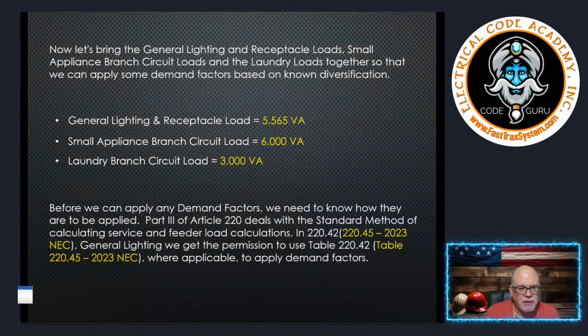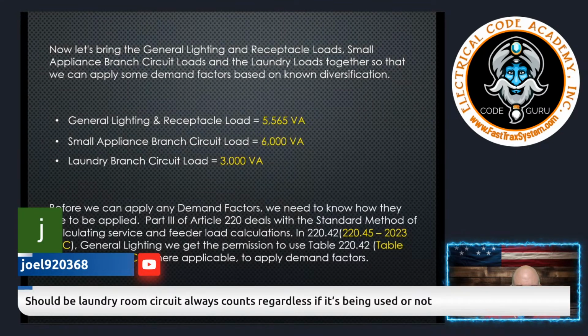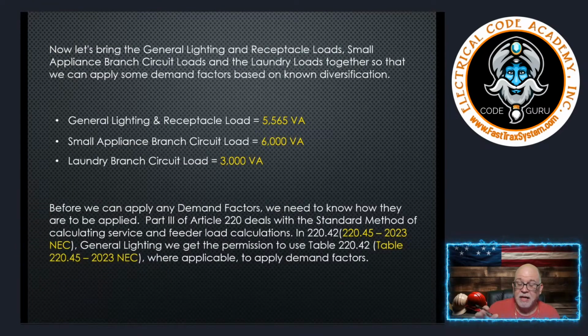Let's see here. Question we had: should the laundry room circuit always be counted regardless if it's being used or not? You have to have a laundry circuit, period. Unless you're dealing with a multifamily dwelling that has a laundry facility on site that is available to all of the tenants or all of the renters, then it doesn't matter whether you use that laundry room or not. You have to have at least one 20 amp laundry circuit.